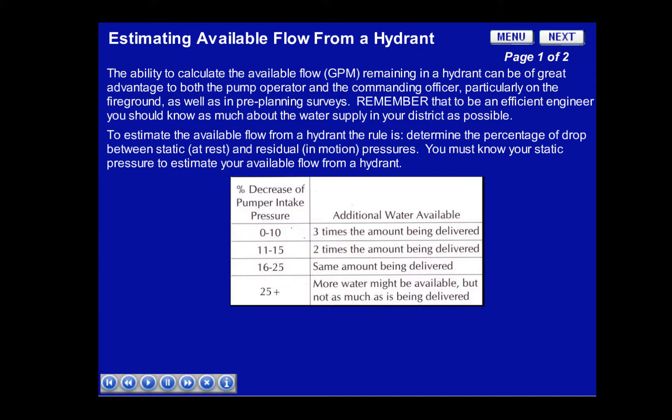This chart shows additional water available using the percentage of loss from the intake pressure. For instance, if you have a 10% or less loss — which is the difference between the static and residual pressure — you will be able to supply three more like volumes as the original line. If you have a loss of 11% to 15%, you will only be able to allow for two more like volumes.